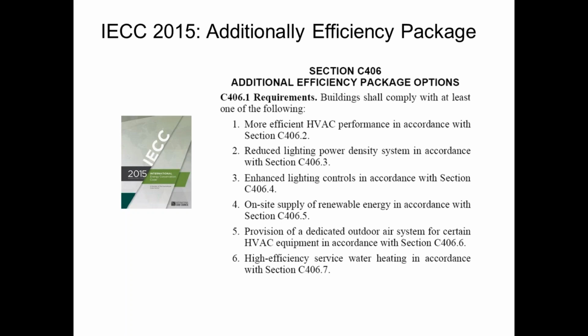I pointed that out in the rooftop example because to get 10% better on the cooling and heating, that means my 80% efficient heat exchanger on my rooftop is now going to have to be 88% efficient. Well, guess what? Nobody makes that, or hardly anybody makes that. I think somebody makes like a little niche 5-ton unit or something, and somebody makes like a super custom air handler rooftop unit that will do it.